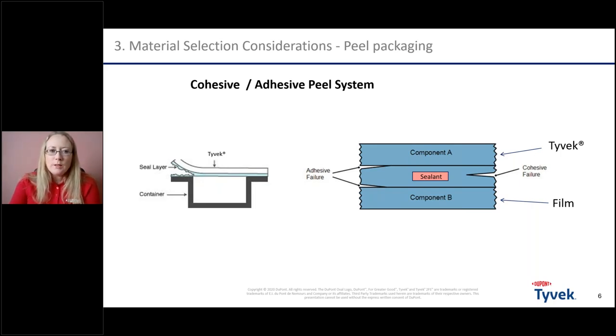So there are different systems. There are even more, but two very common ones are cohesive and adhesive peel systems. When you look at the blue picture here, you have component A, which could be Tyvek, and component B, which could be the film, and you have the sealant in between, which could be linked to the Tyvek or to the film. So principally, an adhesive failure would be when the sealant is coming off from the Tyvek or the film again when peeling, whereas the cohesive failure is really that the sealant is failing in itself.